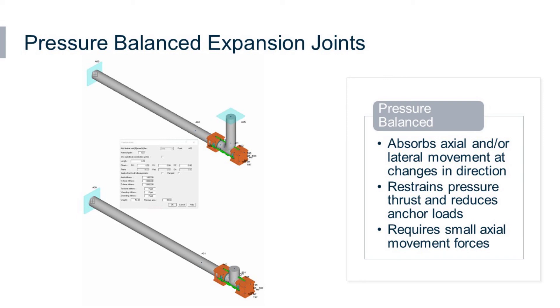It's often used to relieve loads on equipment such as pumps, compressors, and turbines. For the expansion joint to function properly, it's important to understand that the pressure thrust restrained by the tie rods has to exceed the axial movement forces.